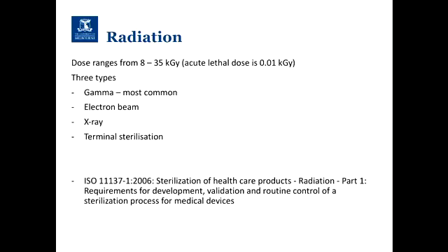So there's a fair few different ways that you can sterilise medical devices. I've put 3 main ones, and really 2 of them have the main part of the market. The first one is irradiation. The most common type of irradiation used for sterilisation is gamma irradiation. That's the most common.